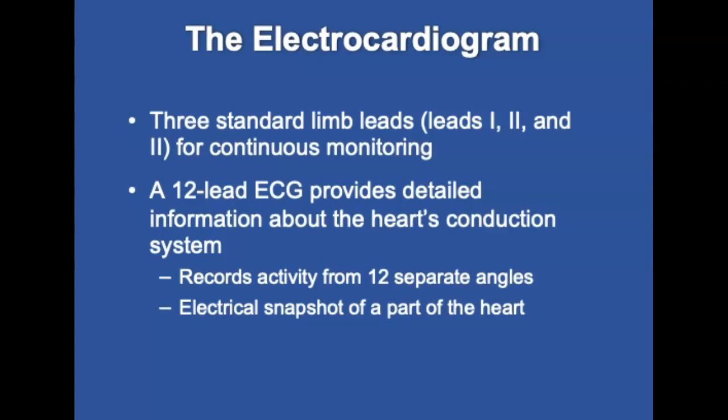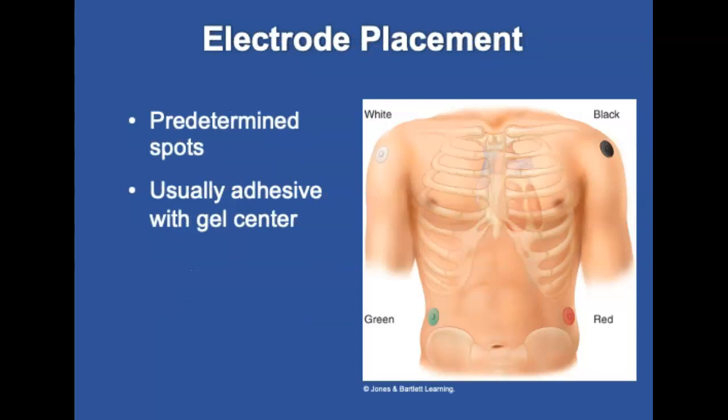Tracings from lead 2 are usually most useful when monitoring, but there are limits to areas of the heart that can be viewed with 3 leads. More detailed information can be obtained from a 12-lead ECG with lead wires and electrodes placed on the patient. Each lead creates an electrical snapshot of a part of the heart, and the monitor records an ECG tracing for each lead for review. The electrodes must be placed in a consistent, predetermined place to get a reliable reading.